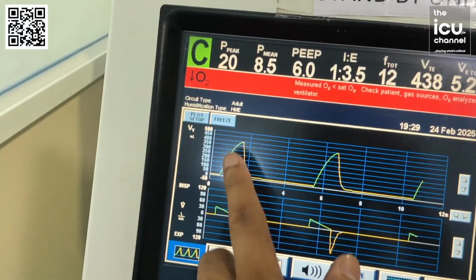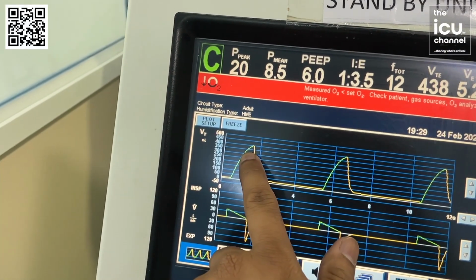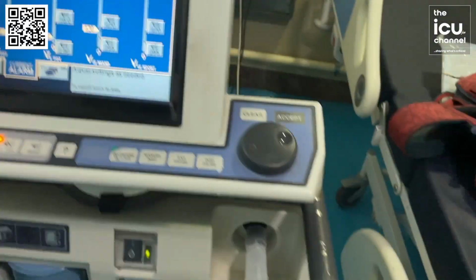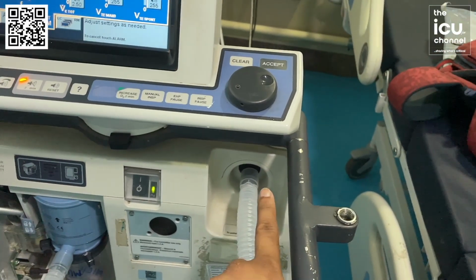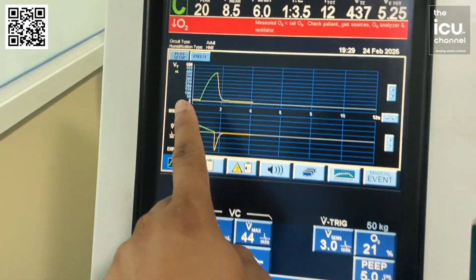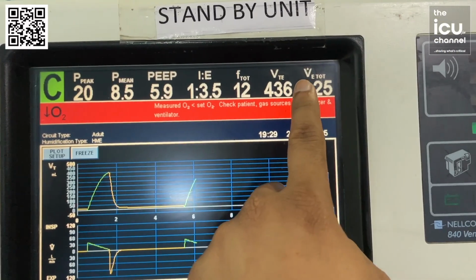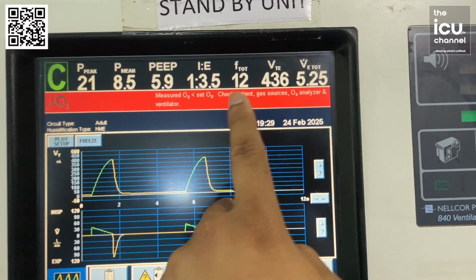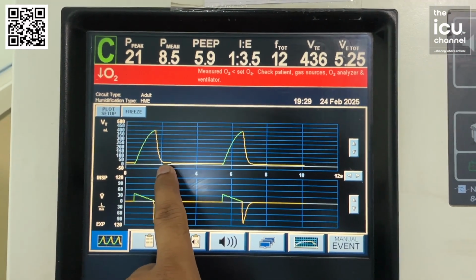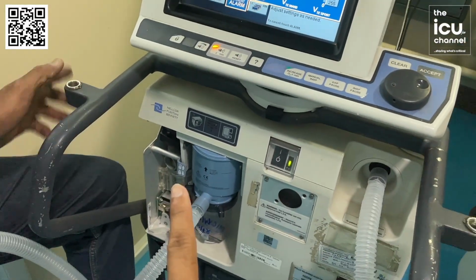Isn't it? Suppose you have set 450, but this is not reaching the 450 mark, that means there is a problem with the inspiratory circuit. It is not delivering properly. But if it is delivering properly and the expiratory tidal volume is not generating properly, that means either there is a leak in the circuit or there is a problem with the flow sensor.